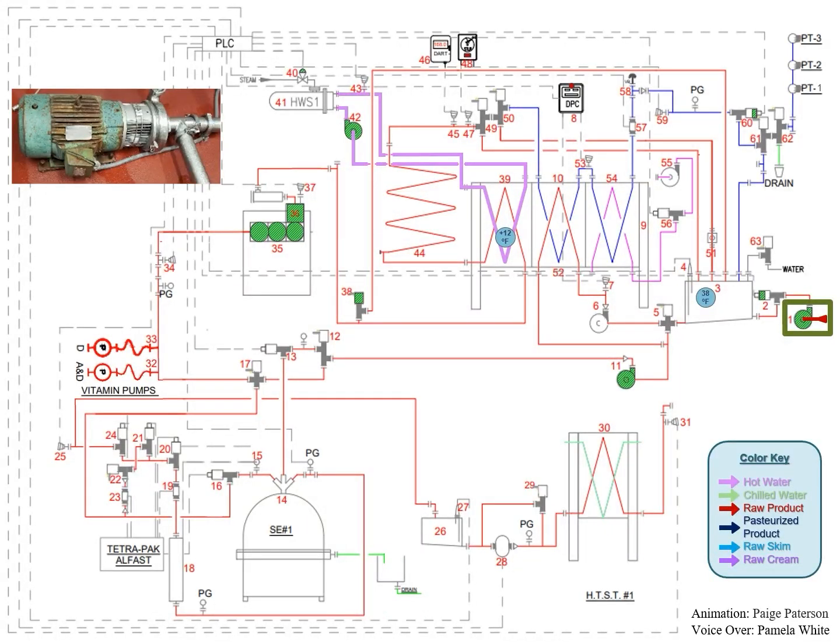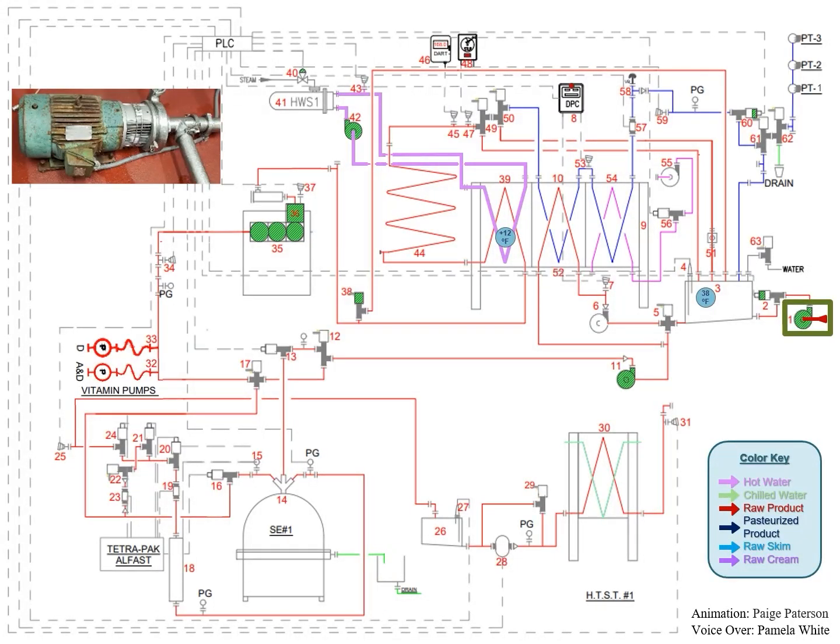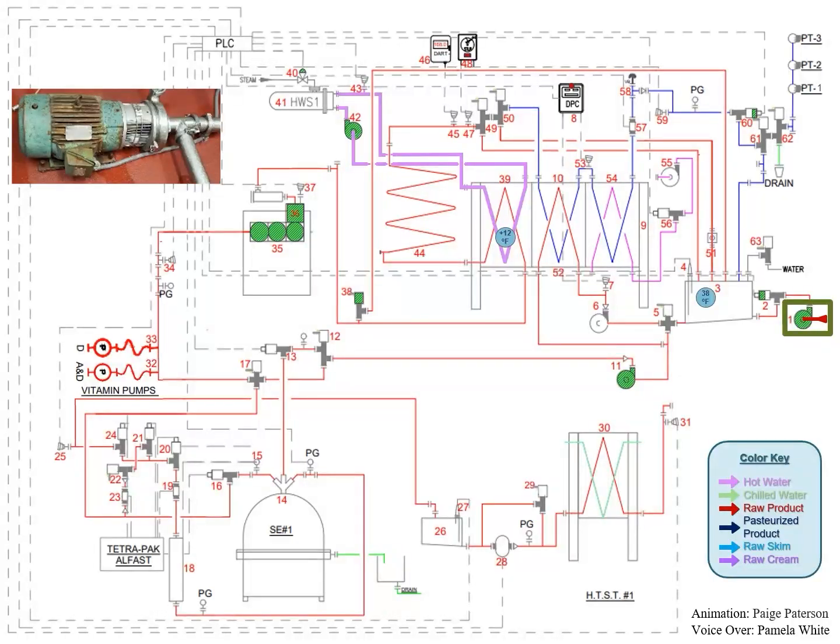When the raw silo tank is full, the additional head pressure in the tank will cause the suction head pressure at the inlet of the raw supply pump to increase, causing it to supply an additional flow rate of 15 to 20 gallons per minute.